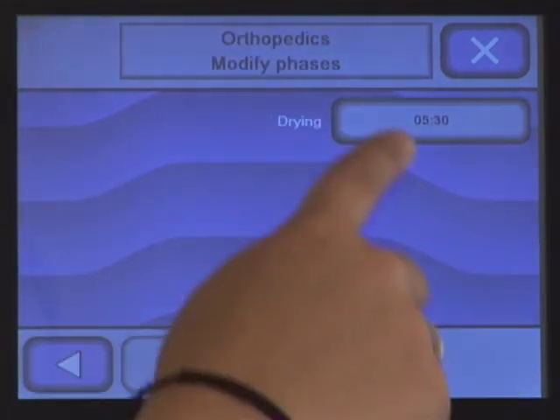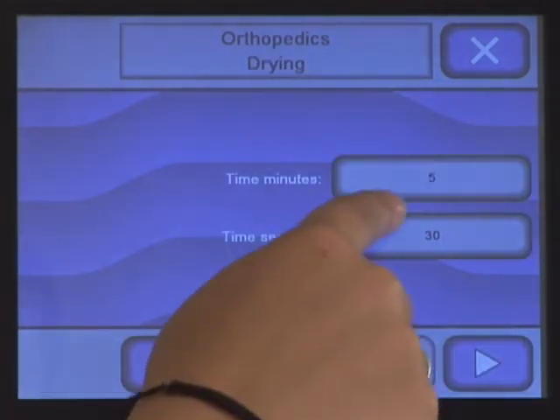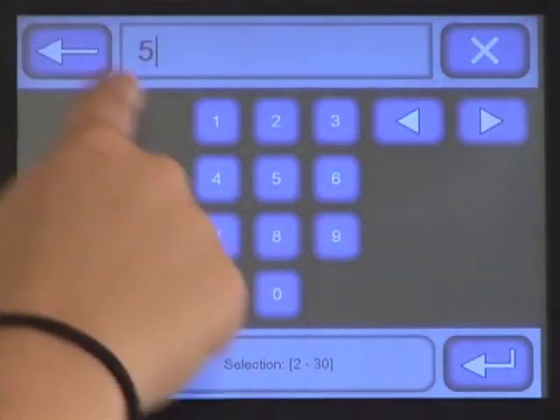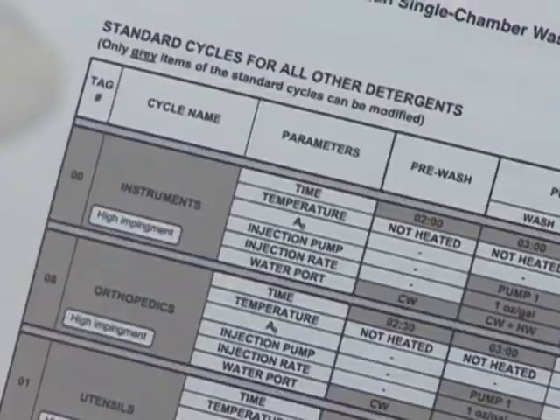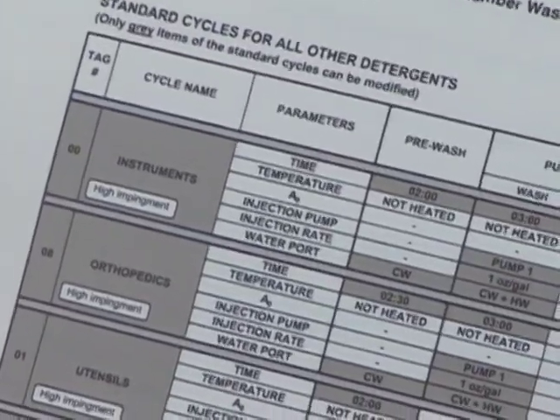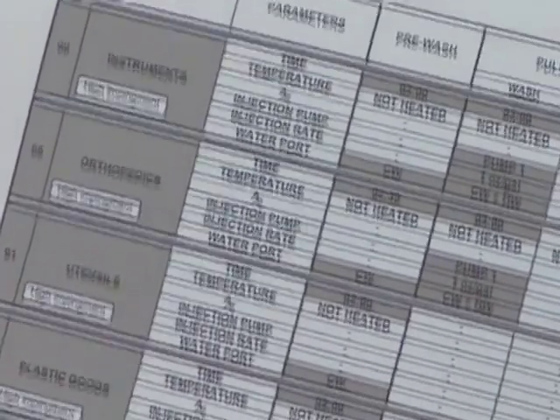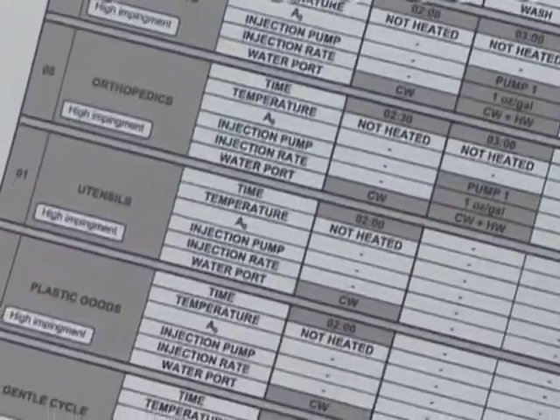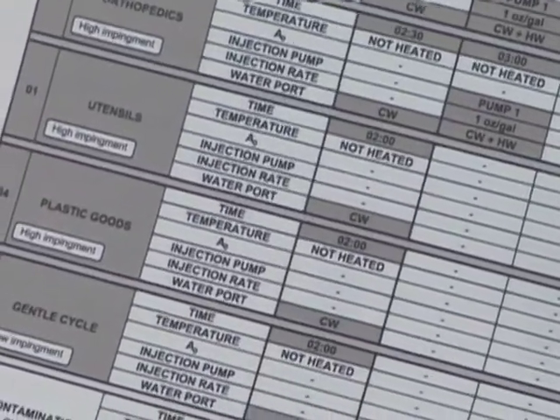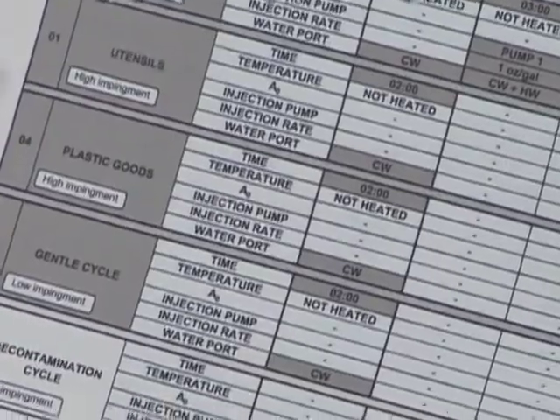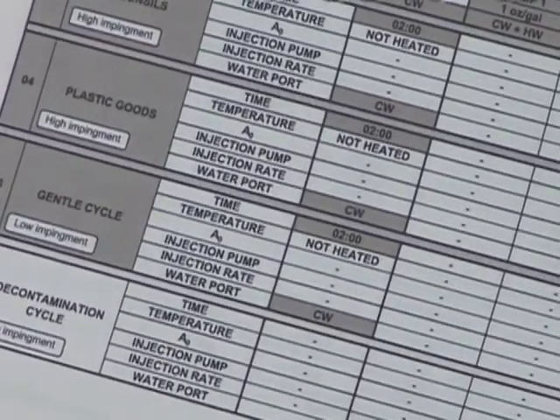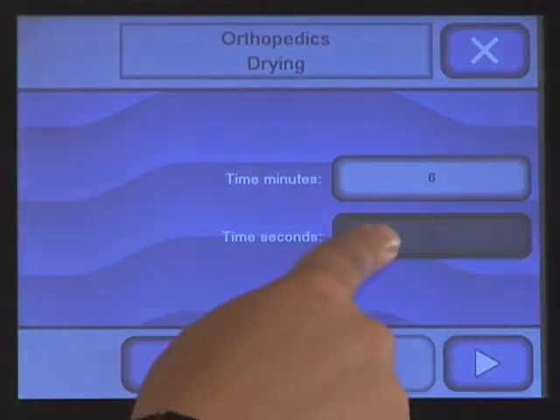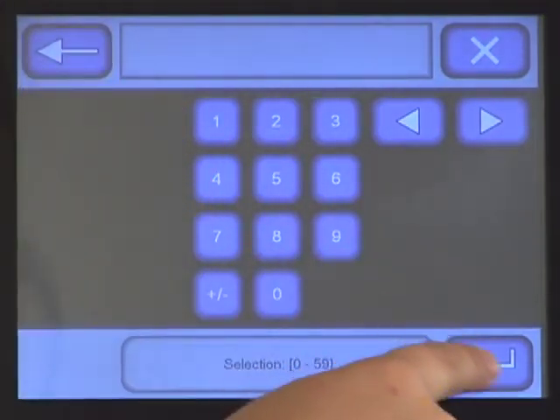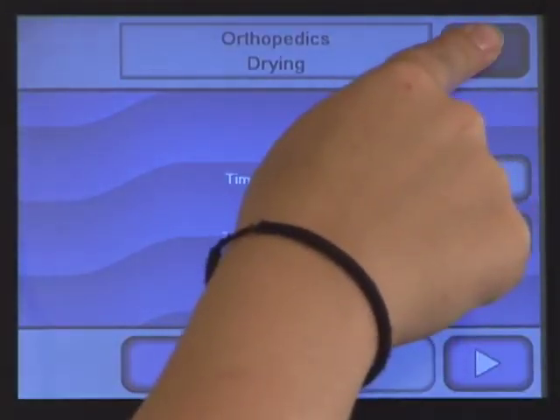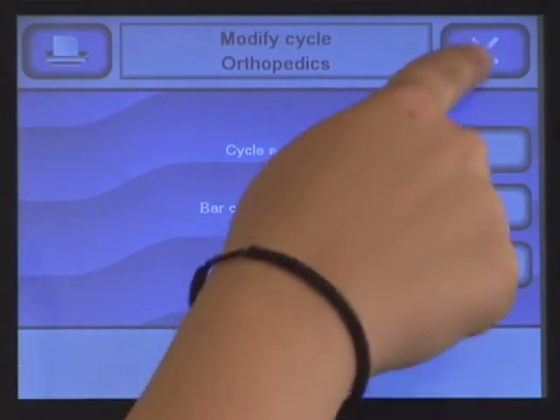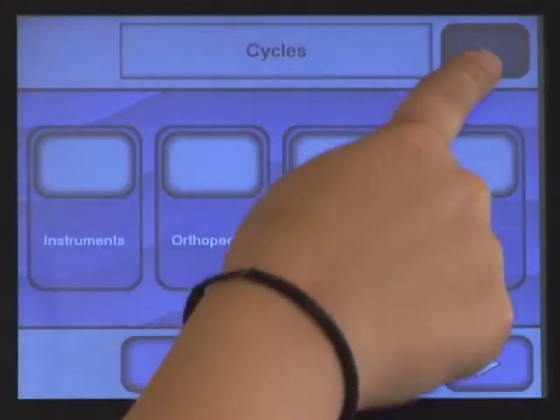Then select which phase you'd like to modify. Follow the instructions to modify the parameters. Keep in mind that to help ensure safe and effective operation, not all cycle parameters can be modified. Refer to the cycle description charts in Section 5 of the Vision Single Chamber Washer Operator Manual. Once you have made the appropriate changes, press Close. Any changes you've made will automatically be saved. Continue to press Close until you've reached the desired screen.